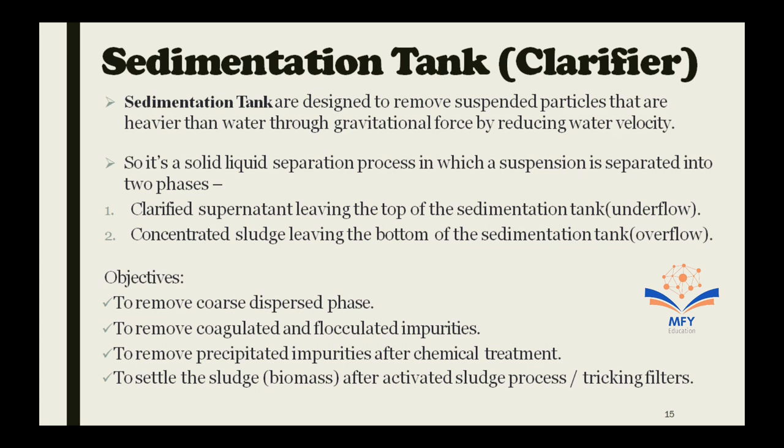Sedimentation tank, clarifier. Sedimentation tanks are designed to remove suspended particles that are heavier than water through gravitational force by reducing water velocity. It is a solid-liquid separation process in which the suspension is separated into two phases. Number one is clarified supernatant leaving the top of the sedimentation tank, which is known as overflow, while the other is concentrated sludge leaving the bottom of the tank, which is known as underflow.